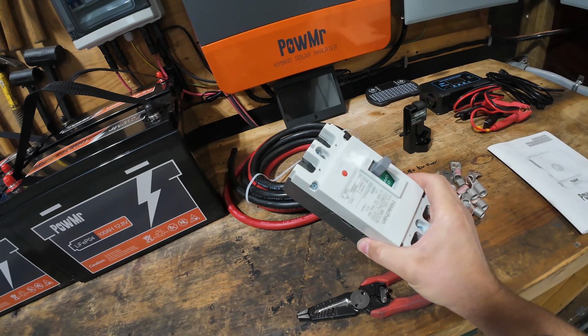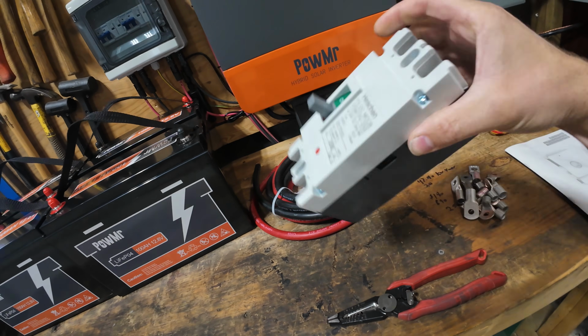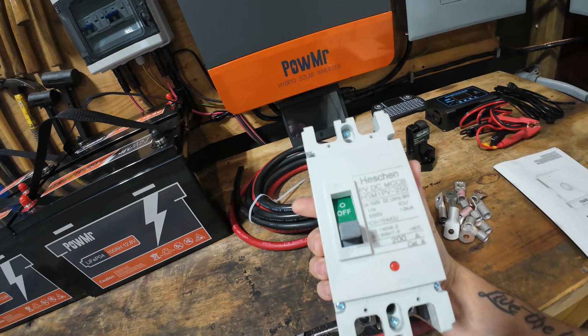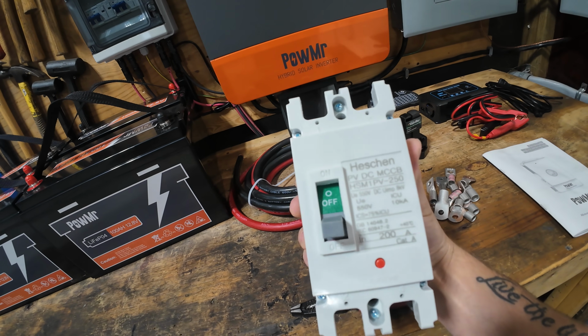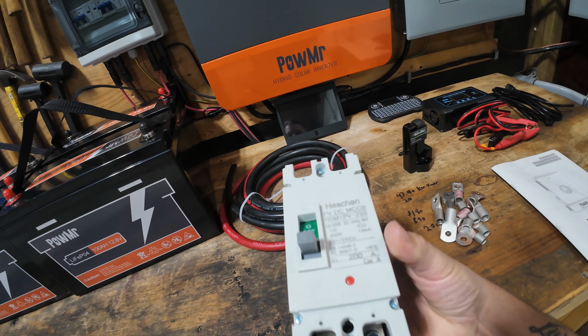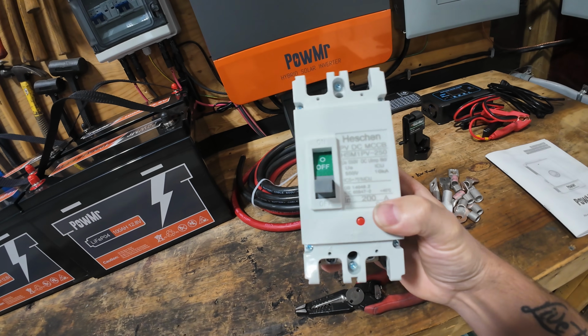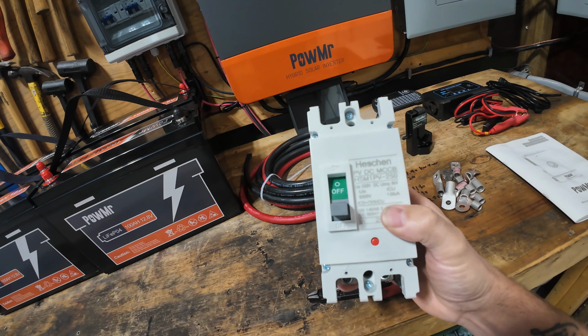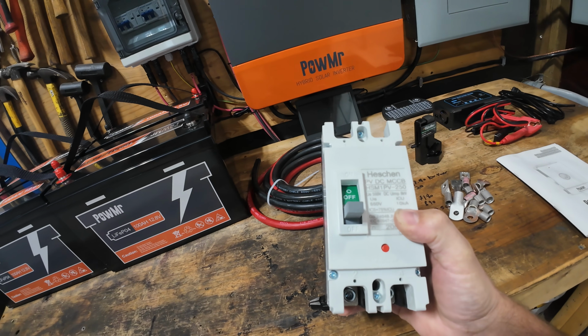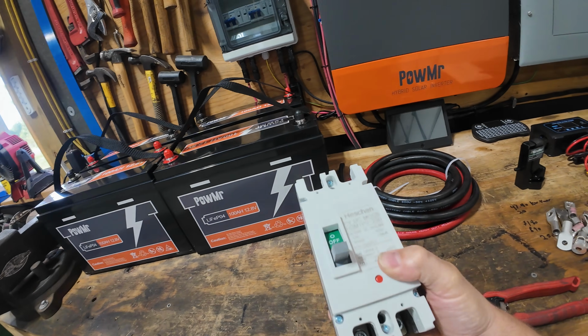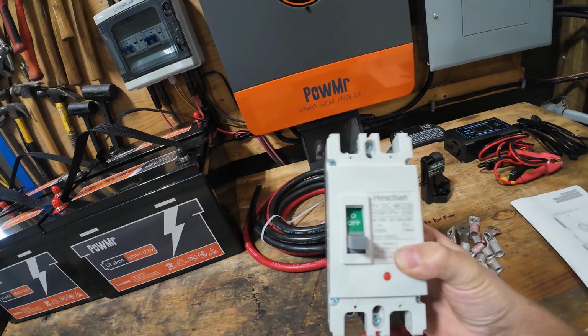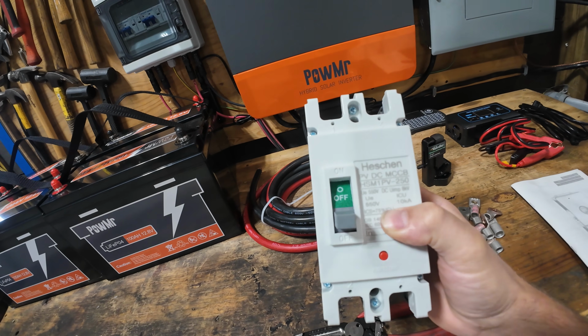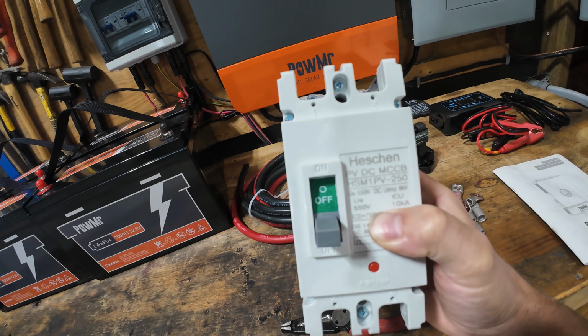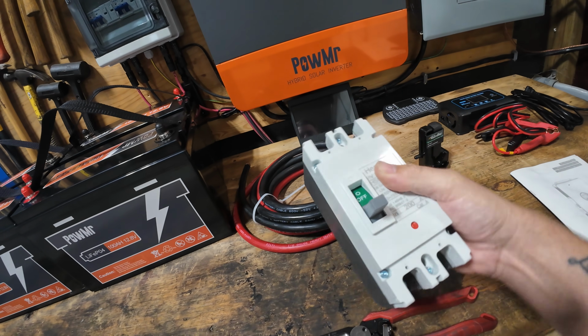I've got myself a 200 amp DC breaker. You want to make sure that these breakers are rated for the power, the voltage that your DC system is going to be producing. So because it's a 48 volt system, your breaker needs to handle at least 52 to 54 volts, because when these batteries are fully charged, they should sit around 54 volts. So I would go over that. In fact, this breaker I bought can actually handle up to 550 volts, but it's a 200 amp breaker, double pole. That's what you need.